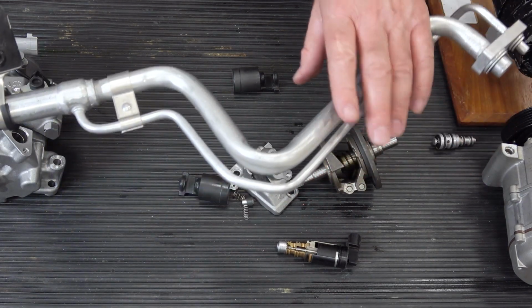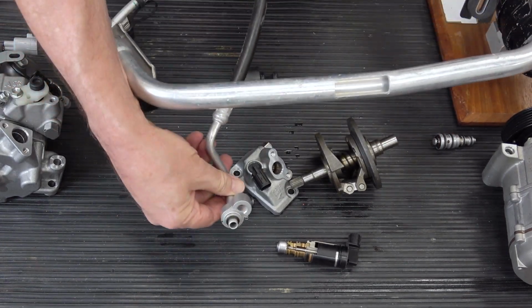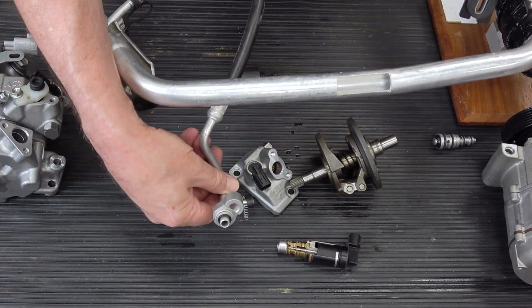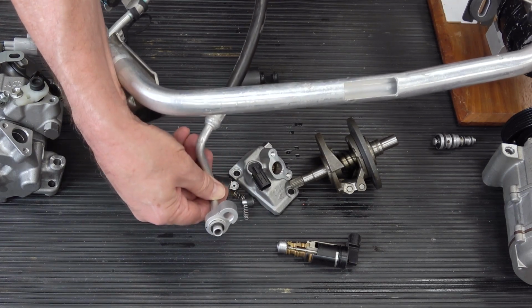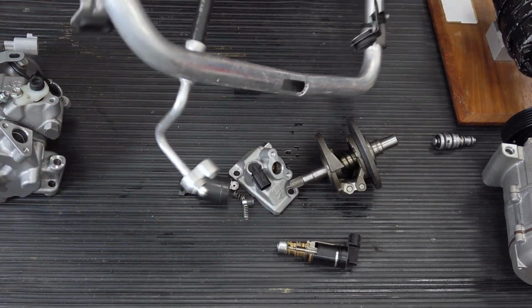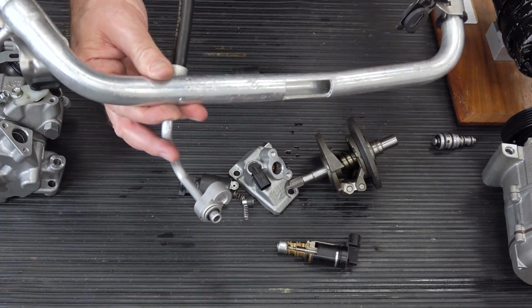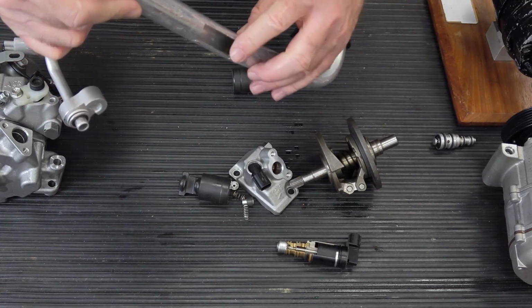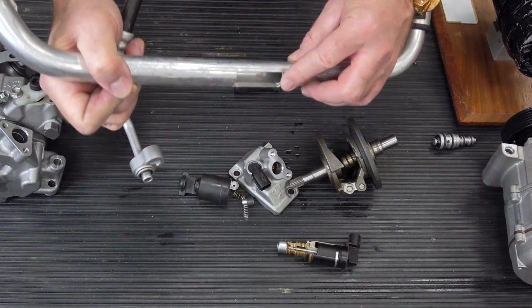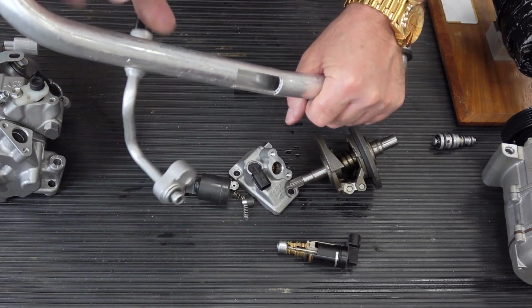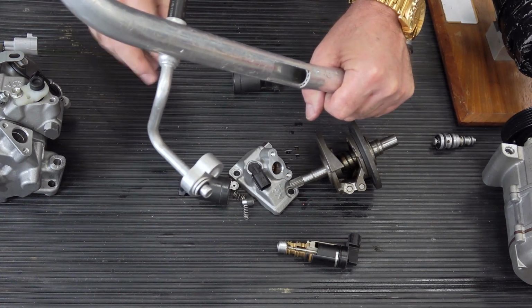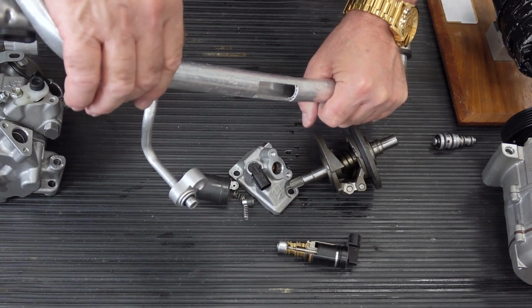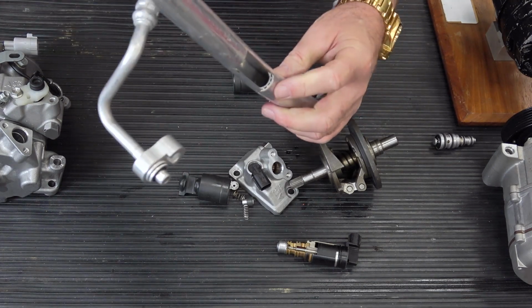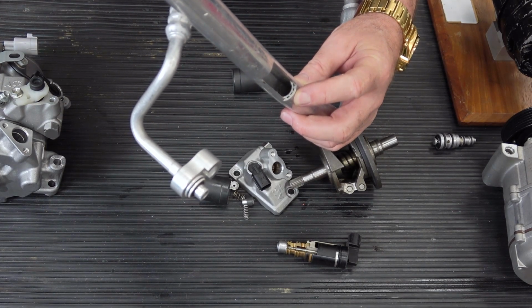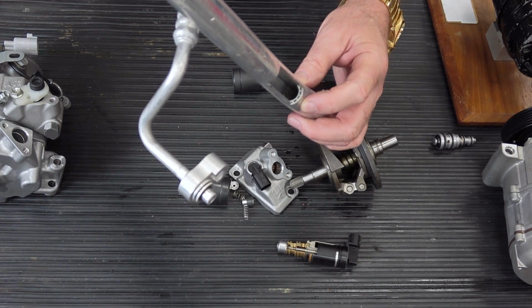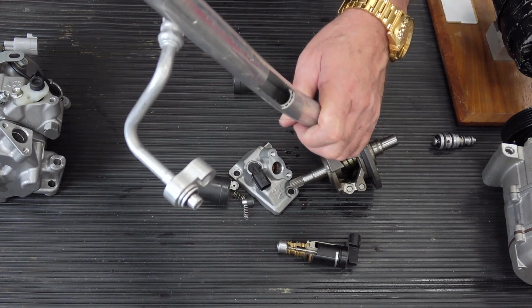So the way this works is this. The liquid refrigerant leaving the condenser is still warm, probably 110, 120, 130 degrees. And if you look, the internal heat exchanger is really what we would call a double walled pipe. If we look inside here, I think you can see that it's just two pipes, like a pipe within a pipe. The liquid refrigerant flows in the narrow area. You can see this little passage right there at the tip of my finger. It flows in the skin between the two pipes.